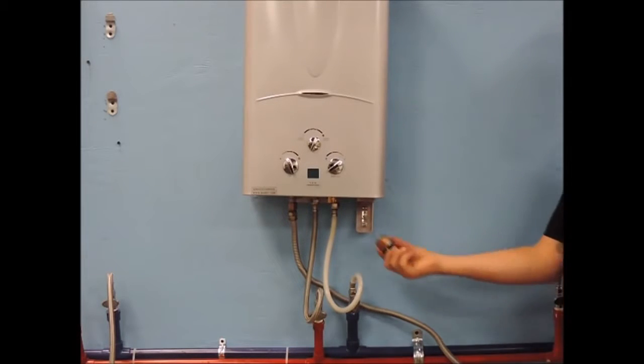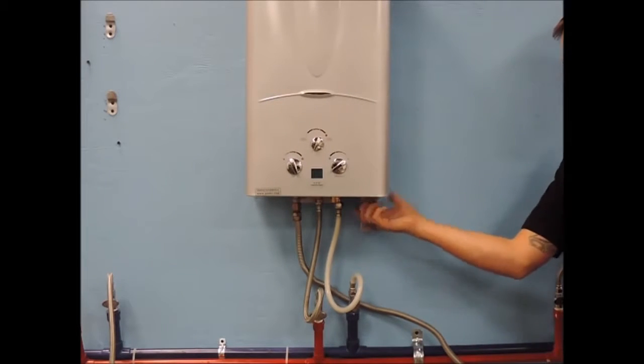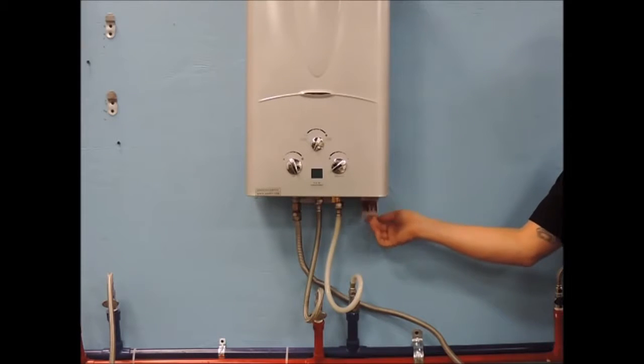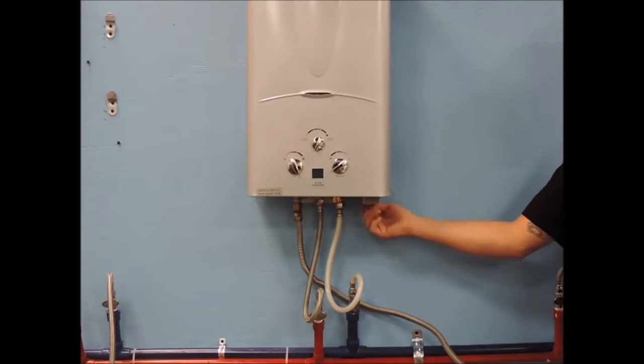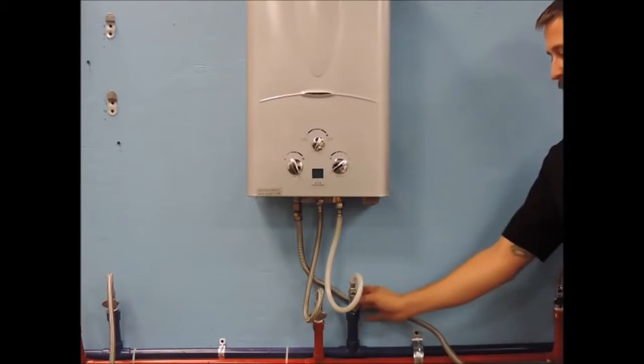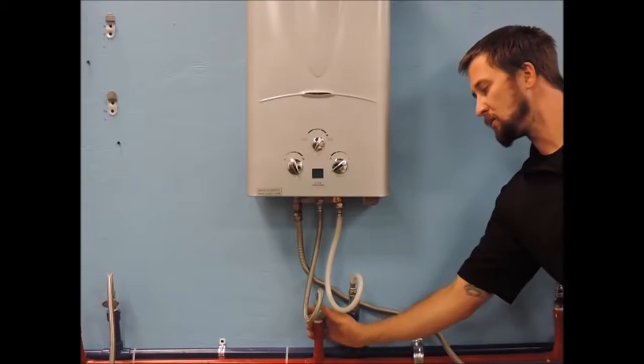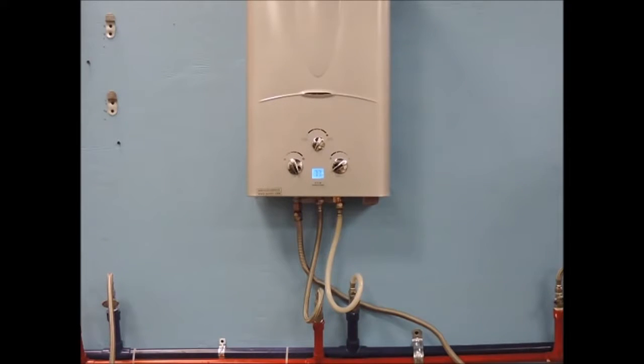We will want to check that the batteries are installed with the correct polarity. Please note that the polarity of the batteries is marked on the inner side of the door to the battery compartment. If at this time you do not hear an audible clicking when water is running through the unit, then please first watch the video Power Gas Troubleshooting Part 1 before moving further.